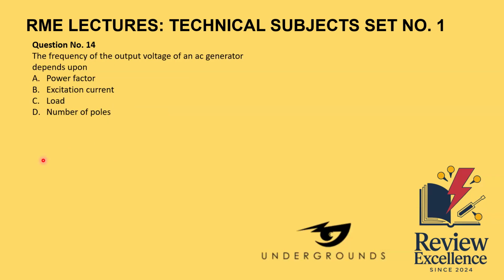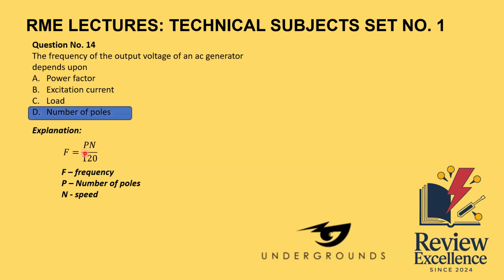Question number 14. The frequency of the output voltage of an AC generator depends upon A. Power factor, B. Excitation current, C. Load, D. Number of poles. Yung formula ng generated frequency ay equal sa number of poles times the speed over 120. Yung F ay frequency, P ay number of poles, at N ay speed of the motor. So ang frequency ay nakadepende sa number of poles. That is letter D.